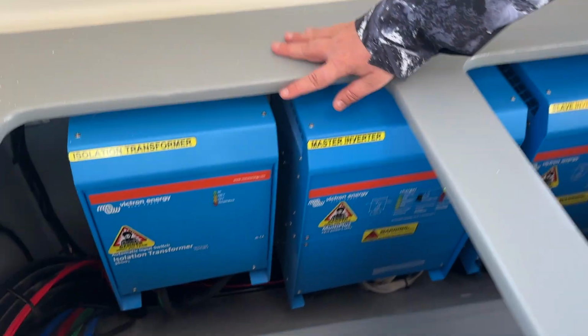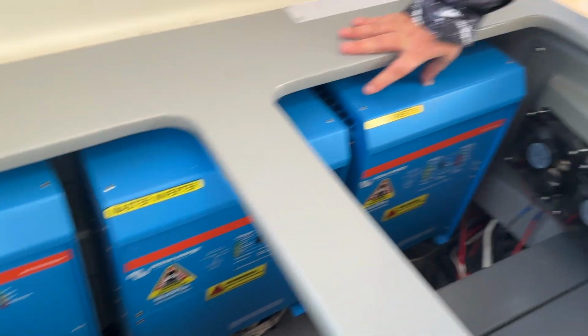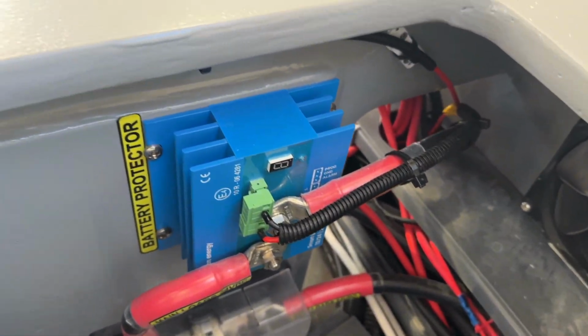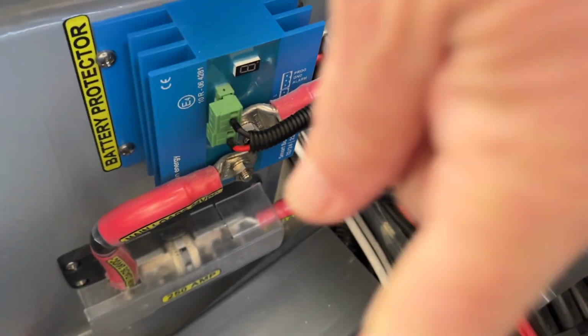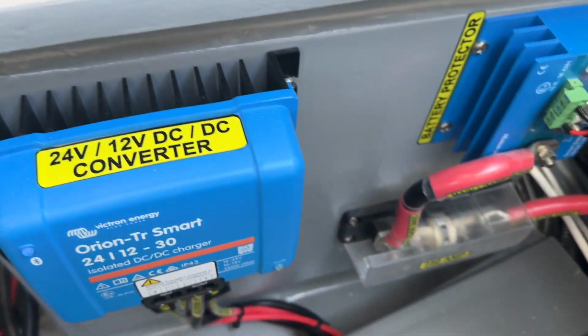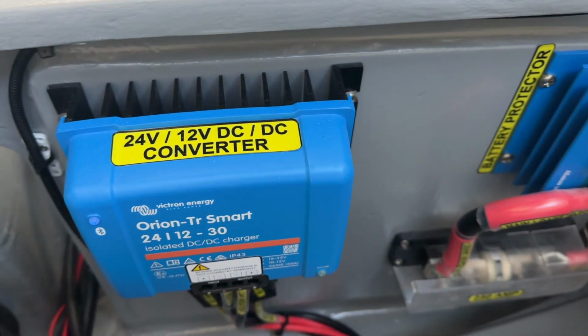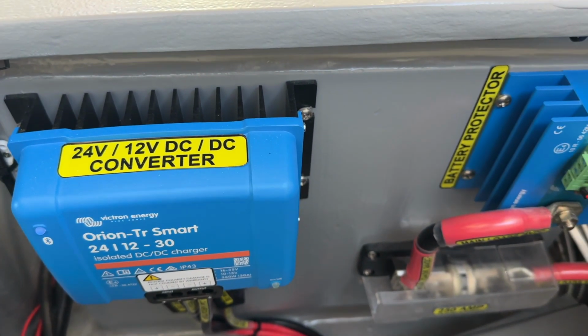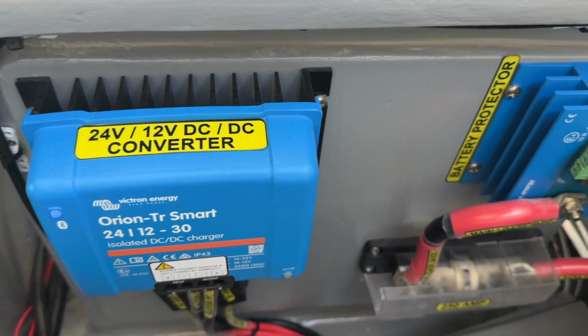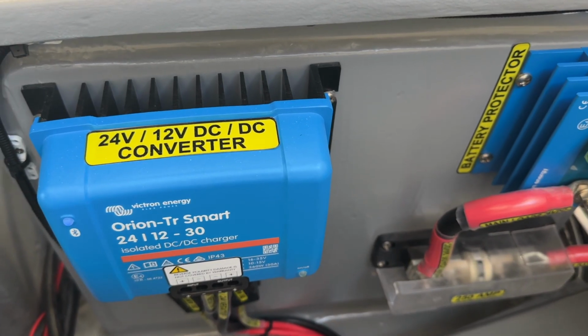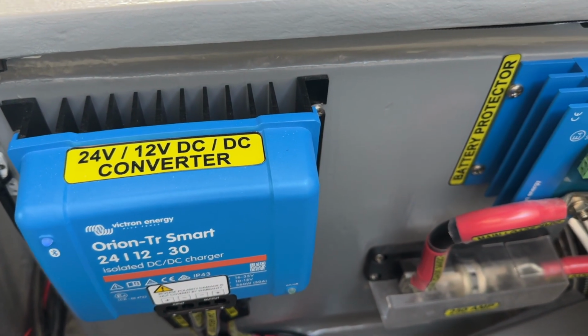Coming onto this side, we have the isolation transformer. You have the master and slave inverter. You have your load battery protector there, SBP smart battery protector, and there, a big 250 amp T fuse below it for your loads to your DB. Next to it, a DC to DC converter - you're stepping your 24 volts down to 12 volts. It's limited, a small little guy, mostly just for instrumentation. We don't use it to power USBs etc. We're trying to use it only for instrumentation, like your navigation, backbones, and so on.